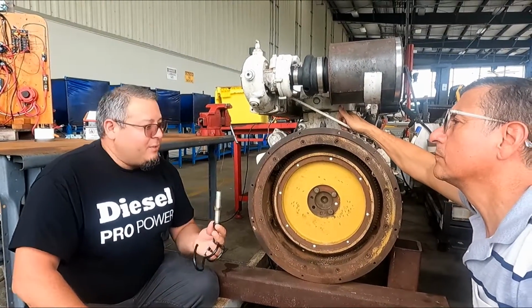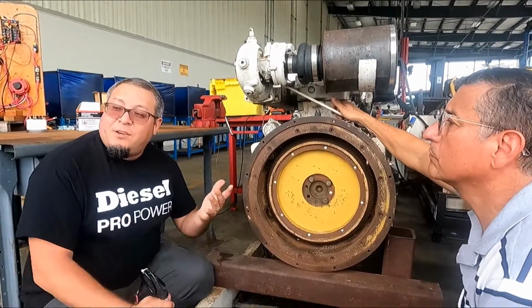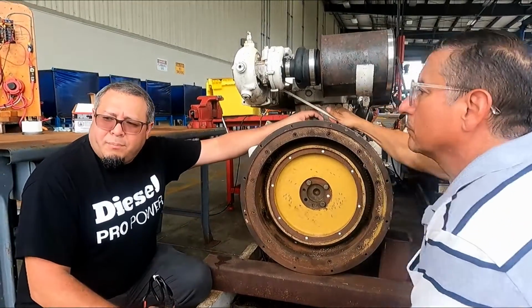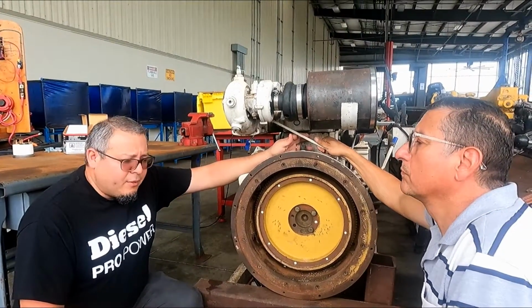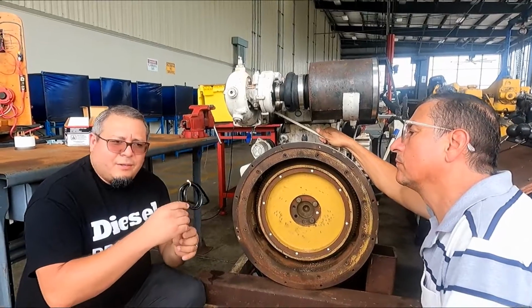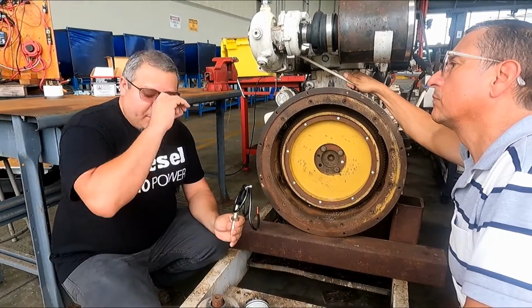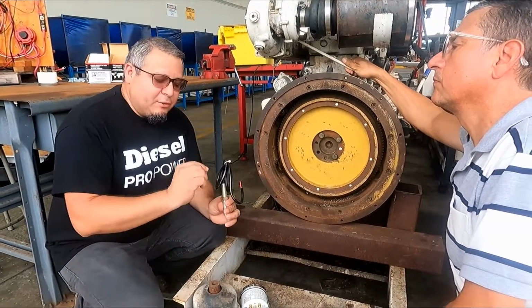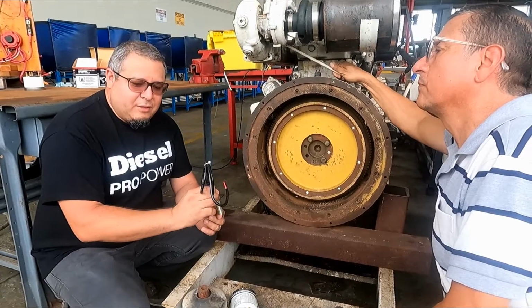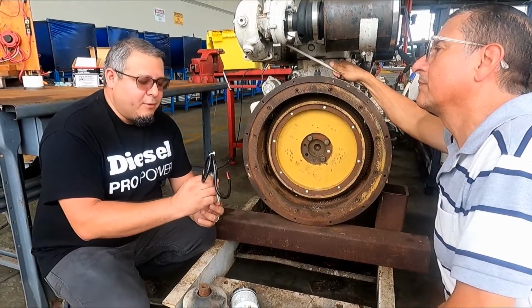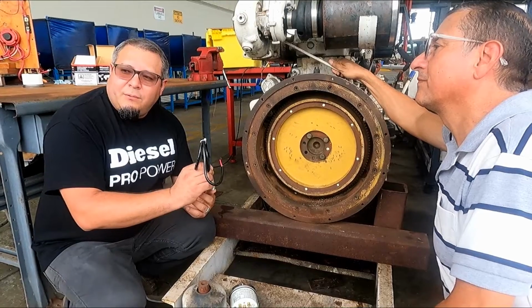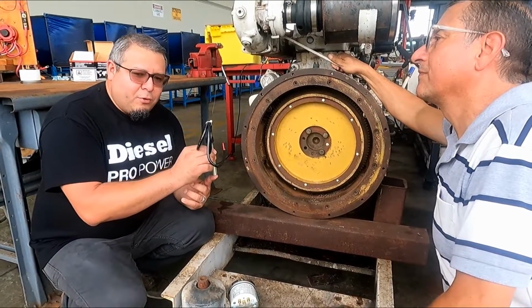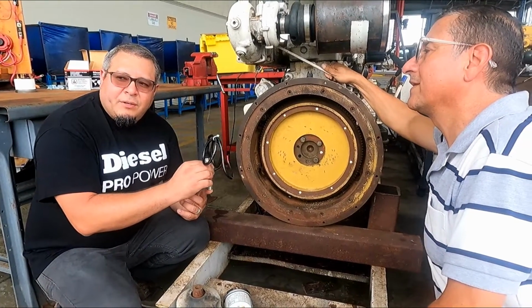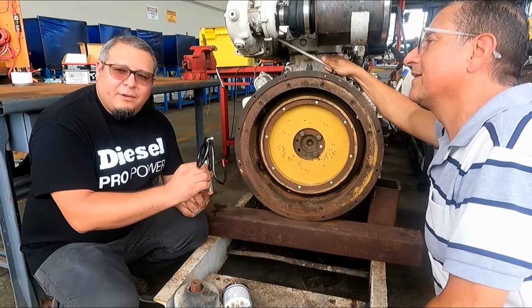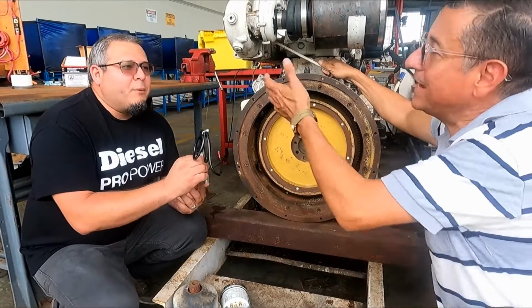To install it is very easy. Typically it comes with a plug on it, so you remove the plug, then thread in the magnetic pickup all the way until you hit the teeth of the flywheel. Once it hits the teeth, go back half a turn, and that'll give enough space or clearance for the magnetic pickup to pick up the signal.